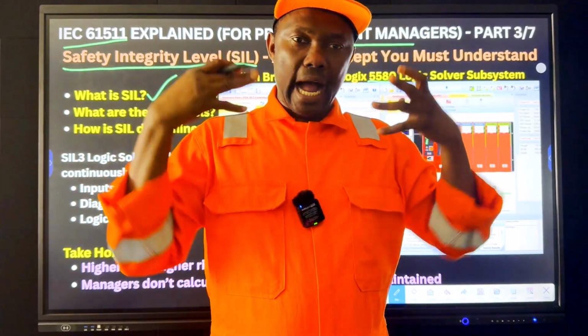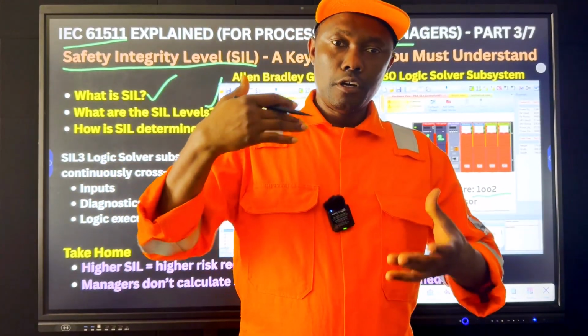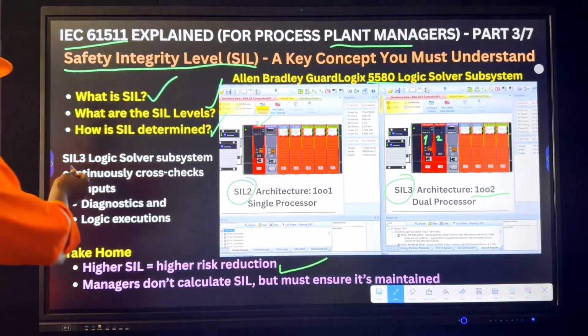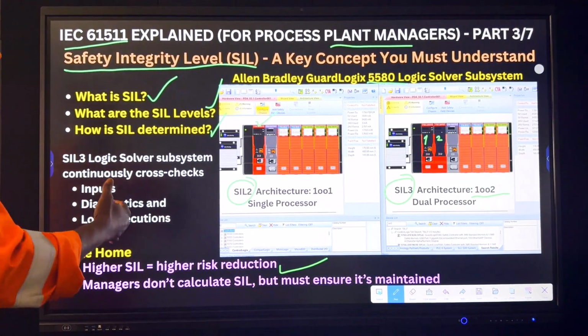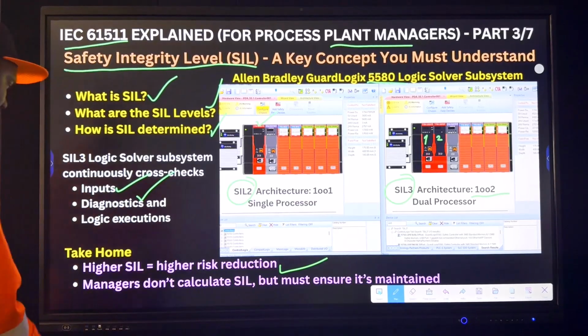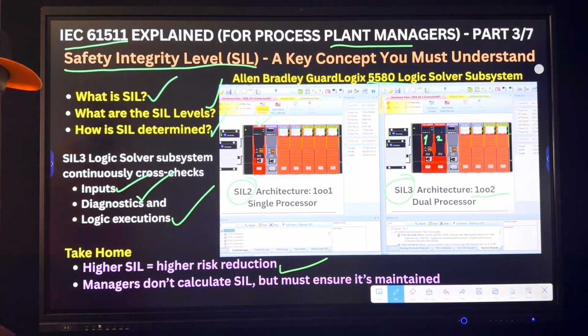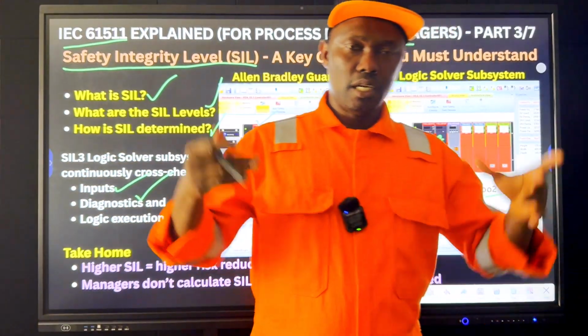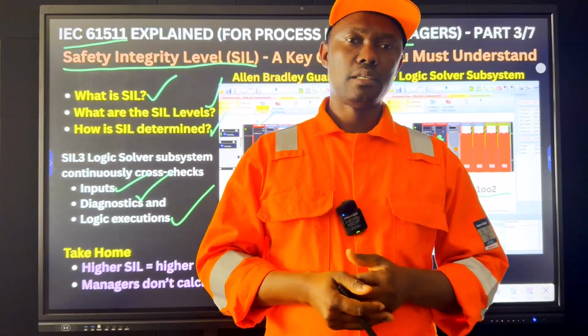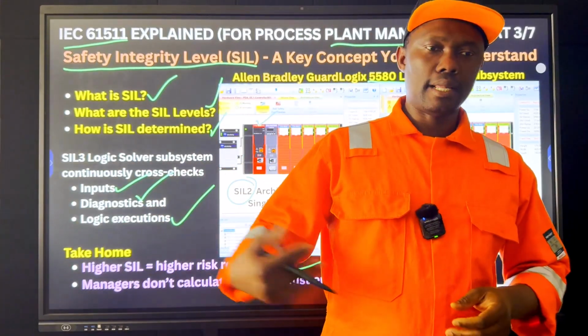For you to achieve that higher level of risk reduction, there are certain features. For SIL3, there will be continuous cross-checks of input, diagnostics, and the logic execution. So if there are discrepancies, the logic solver subsystem moves the process to a safe state through the final element.